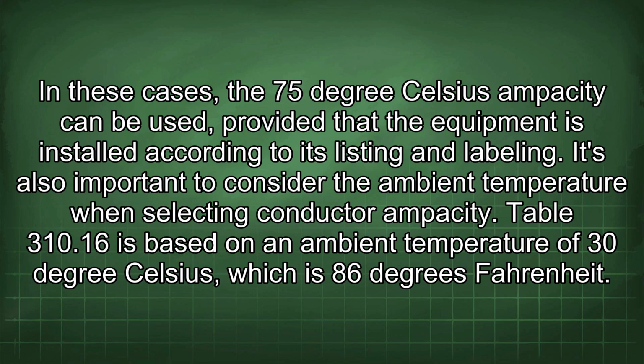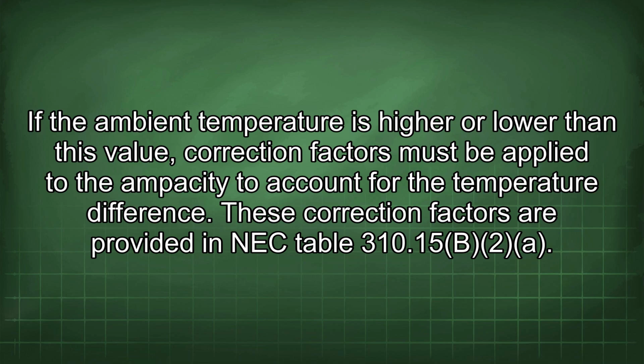It's also important to consider the ambient temperature when selecting conductor ampacity. Table 310.16 is based on an ambient temperature of 30 degrees Celsius, which is 86 degrees Fahrenheit. If the ambient temperature is higher or lower than this value, correction factors must be applied to the ampacity to account for the temperature difference. These correction factors are provided in NEC Table 310.15(B)(2).